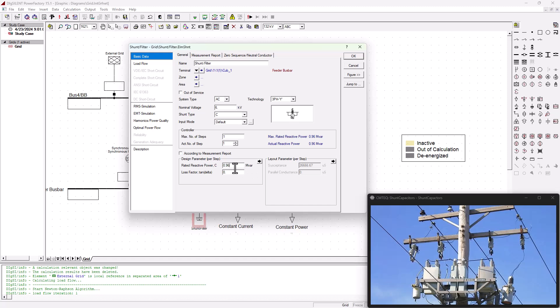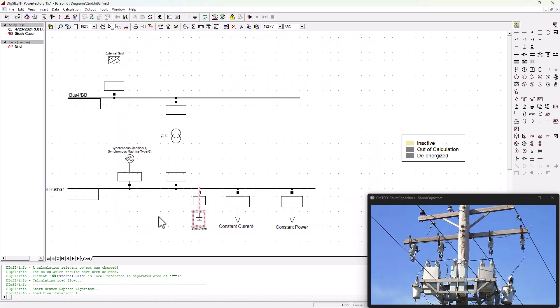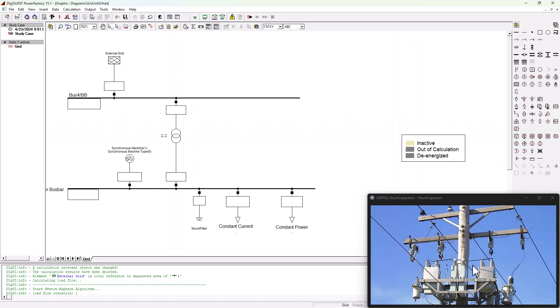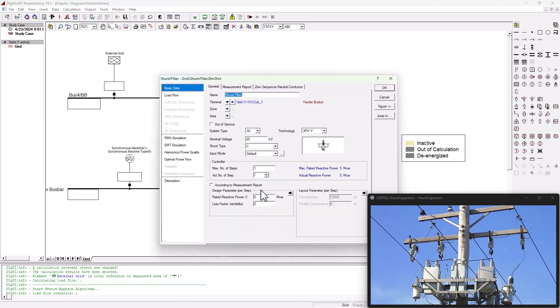Now the rating of our shunt capacitance, we say that it's about 5 MVA reactive. And the nominal voltage that it must be inserted at—that is very important—it must operate on 20 kV. Why 20 kV? Because this busbar here is rated at 20 kV line to line. You're not going to connect a shunt capacitance at a voltage that is rated higher than the actual shunt capacitance—it's not going to work. So it is very important you respect the nominal voltage and also the rating of the shunt capacitance.